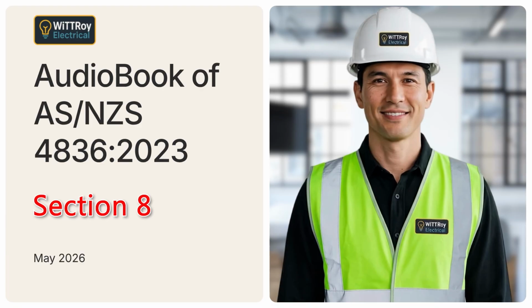In practical terms, insulating mats and covers must be checked carefully. Look for cuts, cracks, holes, contamination, hardening, burns, damage, or anything that could reduce insulation. A damaged insulating mat or cover may give a false sense of protection. For voltages above 650 volts, other standards may apply. So the worker must select the correct insulating cover or mat for the voltage and the task.